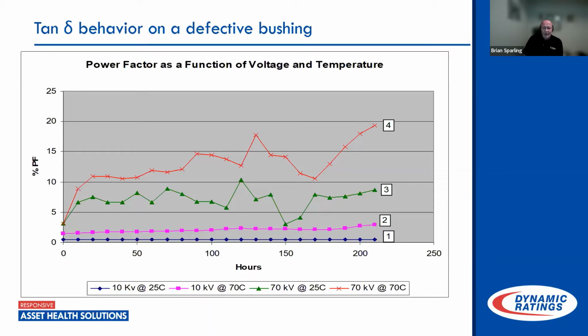Then for trace number 3, we tested the bushing at 70 kV at 25 degrees C. So in other words, at full potential rather than 10 kV. And you can see here that the dissipation factor is jumping all over the place. And trace number 4 shows, at 70 kV and 70 degrees C bushing temperature, that the dissipation factor is all over the map. So this is the function. This is why offline testing sometimes doesn't reveal problems in bushings that are in fact having problems when they're energized at full potential and operating temperatures. This is a key important thing to understand.